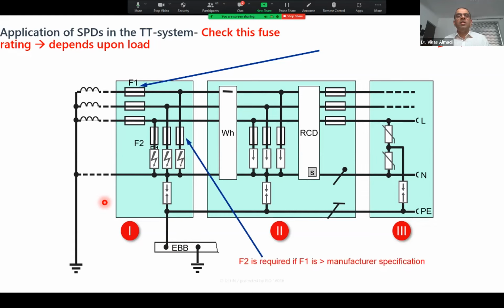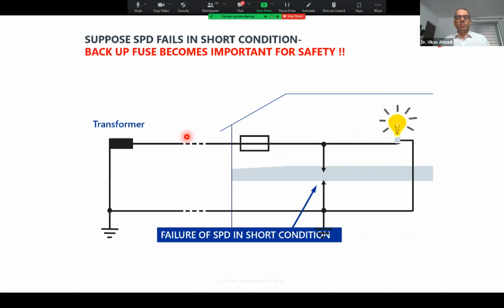But at the same time, to give you a little glimpse about that, these fuses are very, very important for safety. You have to consider SPD as equipment which can also fail. Any equipment can fail, SPD can also fail, and it can fail in open condition or short condition. If it fails in the short condition, what happens at that time, if there is no backup arrangement? So backup arrangement can be done by the mains panel itself, but the rating of the fuse that fits with the SPD is defined by the SPD manufacturer. So the SPD manufacturer will tell you what is the rating of the fuse that it needs in the backup. If your initial rating or input rating is higher than the rating specified by the manufacturer, you have to use additional fuses here. Otherwise, there is no need of additional fuses.